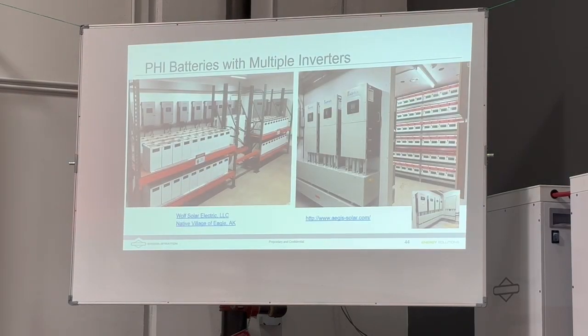Okay, so I promised you I'd show you some pictures where we've got this one, I think is 7 or 8 Sol-Ark 12Ks that are here. And we just recommended using the non-communicating Phi batteries for that. All your batteries are connected on this busing that's here. If you need connections to a bus bar manufacturer, we have some links for you. But this, I think, is maybe 80 or 100 of the Phi batteries powering these 12K inverters. And this is up in a village in Alaska.